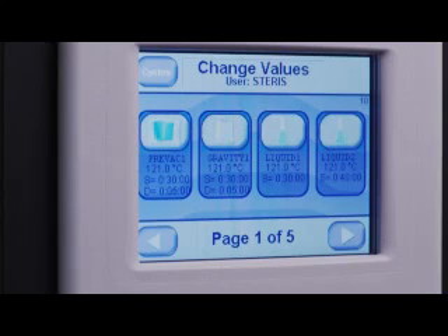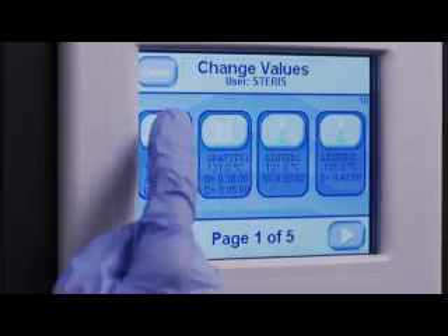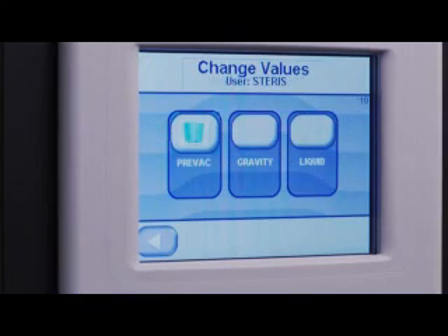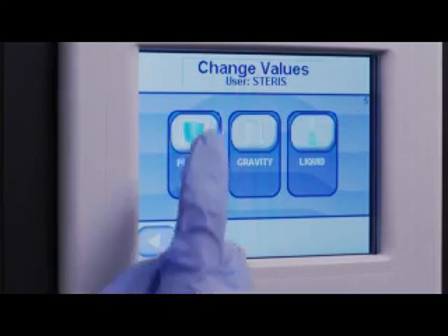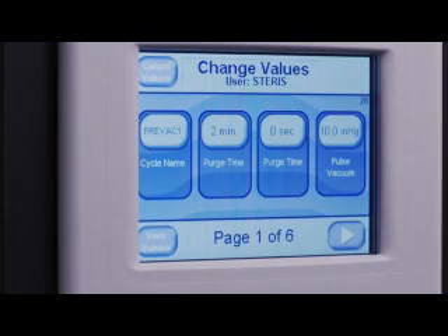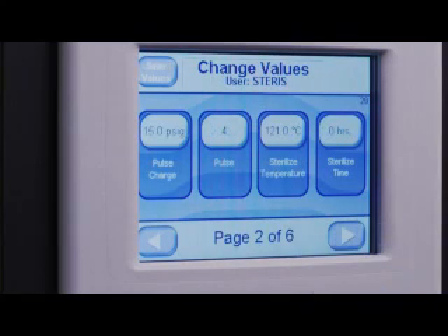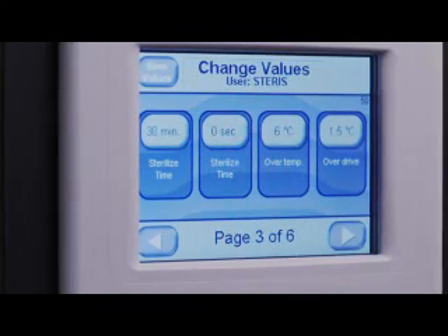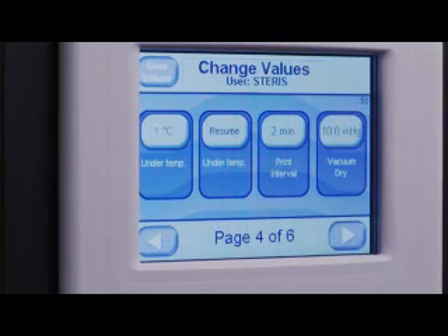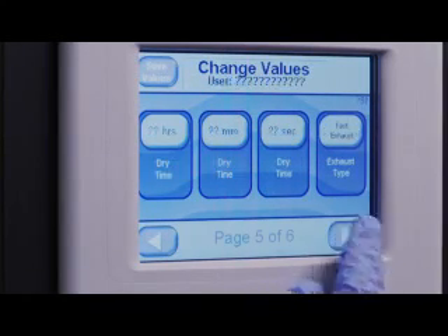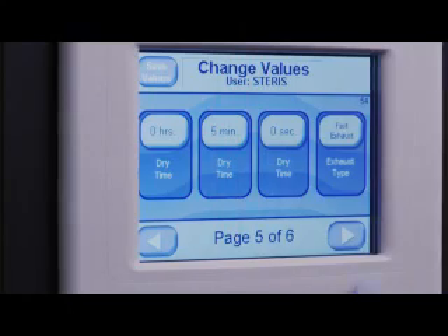will abort. In addition to the previous cycle values, the pre-vacuum cycle will have the addition of vacuum parameters. Programming a pre-vacuum cycle will entail choosing the depth of vacuum, number of steam pulses, and the desired pressure, along with the dry time. The values pre-programmed on the sterilizer should be sufficient for most applications, but should further air removal be required, please contact technical support for additional assistance.